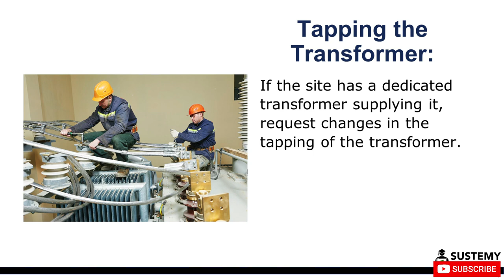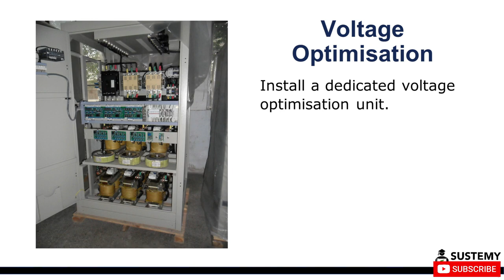If the site has a dedicated distribution transformer supplying it, it may be possible to request the tapping of the transformer be changed in order to lower the voltage. Alternatively, a dedicated voltage optimization unit could also be installed.